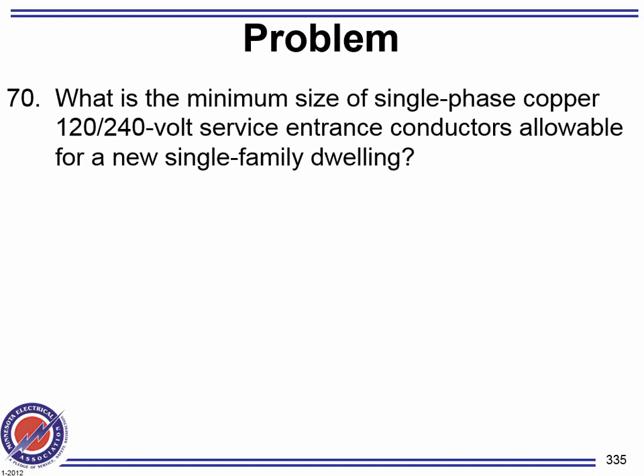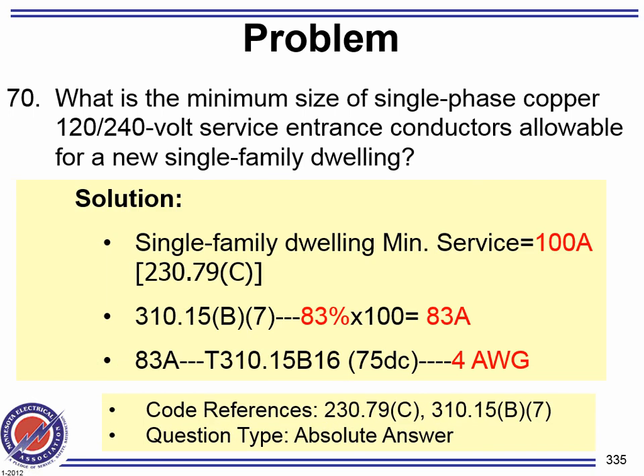One more if you guys are good. For a new single. Okay. So 100 amp. So here's your 100 amp. That's a 100 amp service. In 2014, guys, there used to be a nice table. Oh, by the way, you know what's happening to that table? It's coming now in 2017. In 2017, they're putting it in Annex D. They're not changing the rule, but they're putting it in 2017. Anyway, if you go there, it says if you're doing a single family dwelling, multiply by 83%. So take your service, and that'll get you 83%.